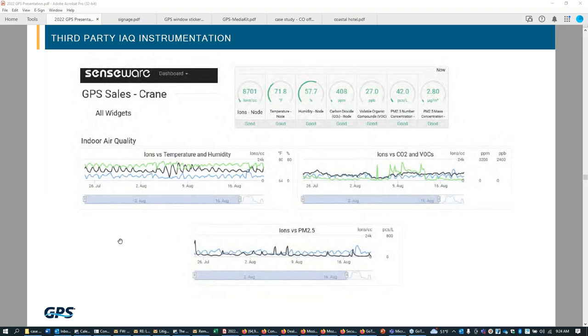GPS doesn't sell a suite of IAQ instrumentation, but I've done a lot of field work with third-party applications. Senseware is one of the companies that I'm more familiar with. I've done a lot of field studies with them. They actually have an IAQ instrument that can measure temperature, humidity, carbon dioxide, VOCs, different PM levels, in addition to ions. So I've used this equipment quite a bit. It allows you to generate some really good data as it relates to the IAQ parameters in the space. They've got tremendous reporting, tremendous analytics, and this sounds like a commercial for Senseware, but it's not.